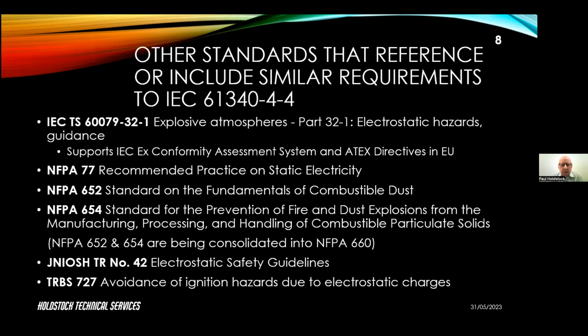Just a quick look at the other standards. And I say I'm not going to go into detail about these because they all, in their own way, either reference the IEC 61340-4-4 or contain very similar requirements. So the first of those I've already mentioned is the 60079-32-1. And this is an IEC standard that supports the IECEx conformity assessment system and the ATEX directives in the European Union. NFPA 77 is a North American standard, and it's the recommended practice on static electricity, which is very similar in scope and content to 60079-32-1. And then there's two specific standards on combustible dusts in NFPA, and that's NFPA 652 and 654. And these are currently being consolidated into one document, NFPA 660.